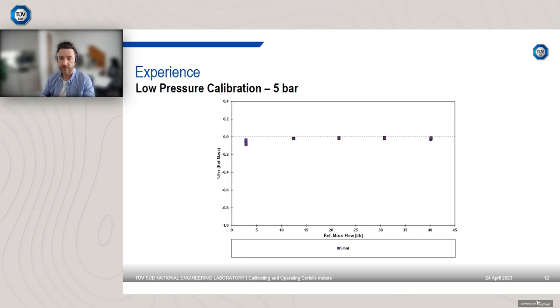What I'm showing you here is a 5-bar calibration. On the x-axis we've got the reference mass flow in tons per hour. On the y-axis is the percentage error of the mass compared to the reference mass. So this is the Coriolis meter mass compared with the primary reference mass at 5-bar. You can see that we're close to specification, slight under reading, but the mass factor could be adjusted. So the mass factor for this device could be adjusted, and you could bring the results up to the 0 line, whether you need to or not. It looks like a very good calibration.